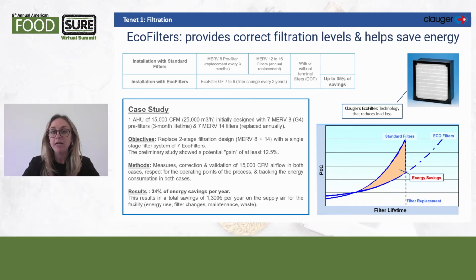To illustrate these filters and their benefits, in one case, our engineers wanted to optimize the filtration costs for a client with a 15,000 CFM air handling unit. This unit was designed with 7 MERV 8 pre-filters and 7 MERV 14 filters, for 14 filters total. Our objective was to reduce the overall number of filters without losing performance or sacrificing the level of air quality. To ensure this, we measured and validated that the 7 eco filters, which combine the MERV 8 and MERV 14 filters into one, had no performance loss. After we validated that, our preliminary study had shown potential of 12.5% in savings, but after we implemented it, we were able to actually generate 24% of savings. This percentage was 1,300 euros annually of energy cost, filter replacement, maintenance cost, and waste cost.